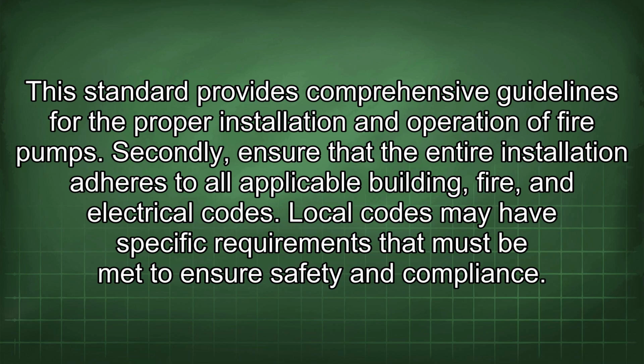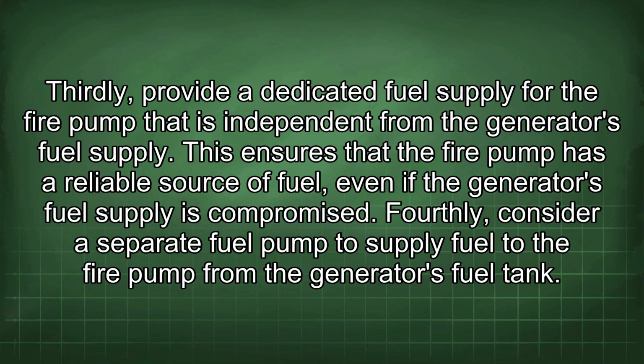Secondly, ensure that the entire installation adheres to all applicable building, fire, and electrical codes. Local codes may have specific requirements that must be met to ensure safety and compliance. Thirdly, provide a dedicated fuel supply for the fire pump that is independent from the generator's fuel supply. This ensures that the fire pump has a reliable source of fuel, even if the generator's fuel supply is compromised.